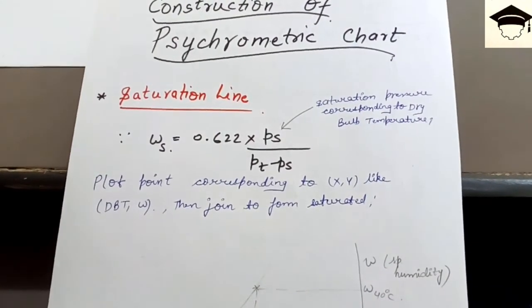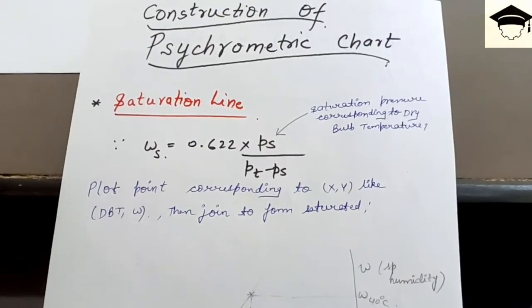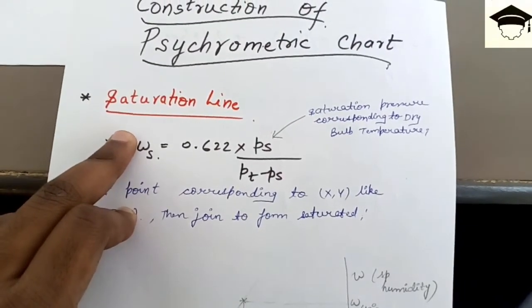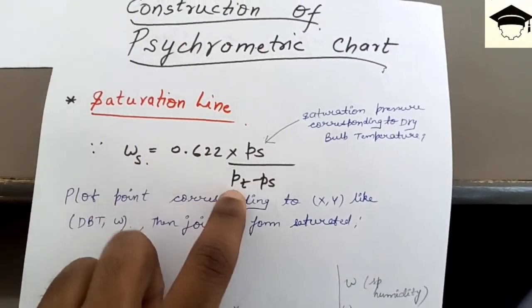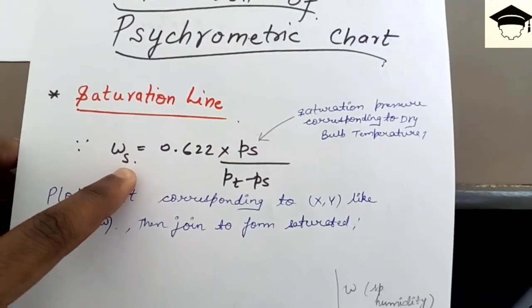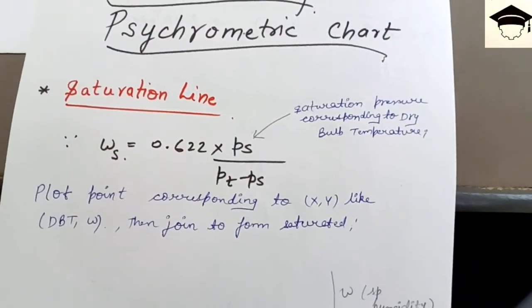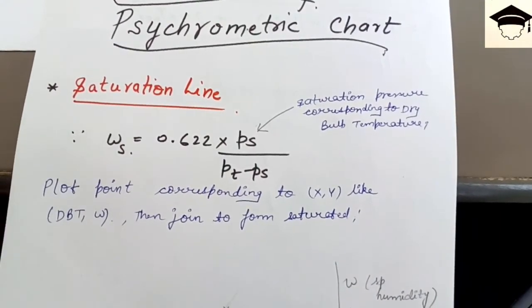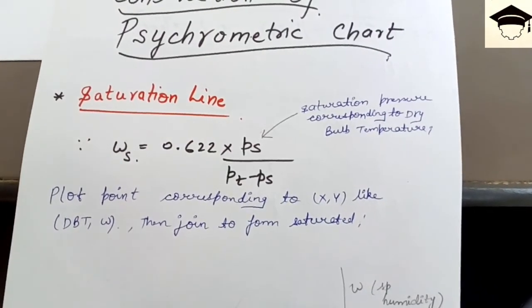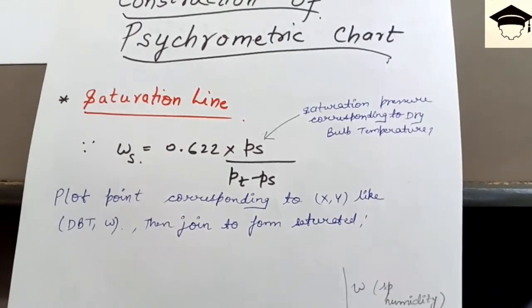Saturation line: on the saturation line the relative humidity is 100%. The specific humidity formula is Ωs = 0.622 × Ps / (PT − Ps), where Ps is the saturation pressure corresponding to dry bulb temperature and PT is the total pressure. If drawing at atmospheric pressure, PT = 760 mmHg or 1.01325 bar.